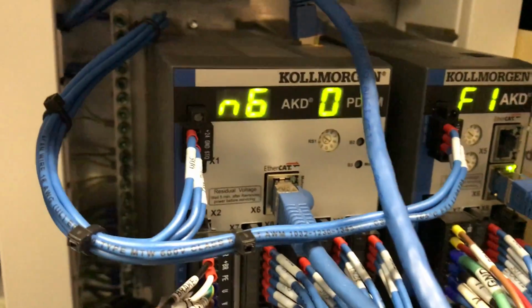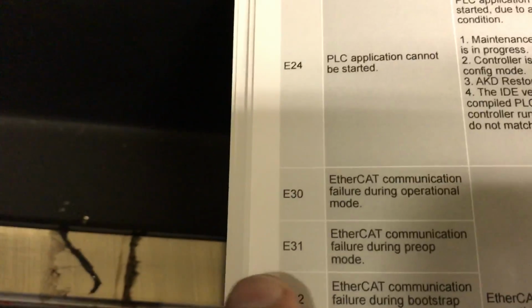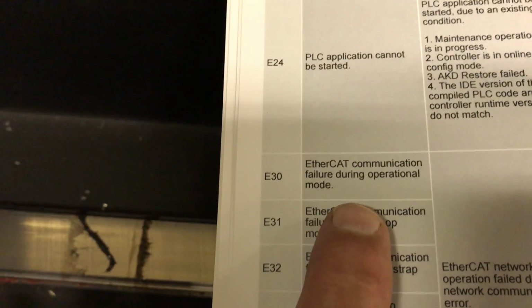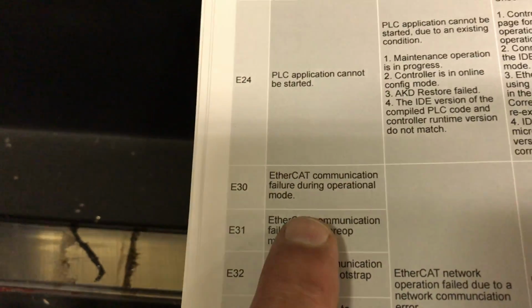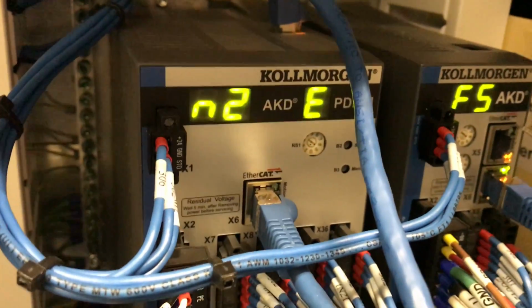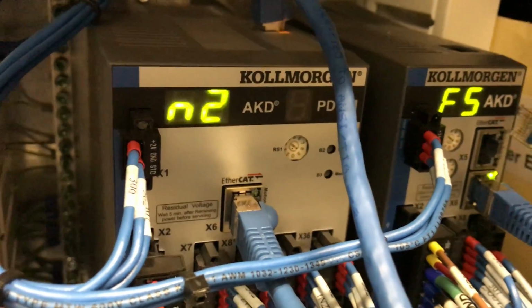And now in that error window we have an E30. So we can come to this same book, which you can find online, and look up the E faults, error codes. So here we are. We have E30. It says EtherCAT communication failure during operation mode. And that's what we did. The line was broken. So these error codes are pretty serious, and you'll have to do something.